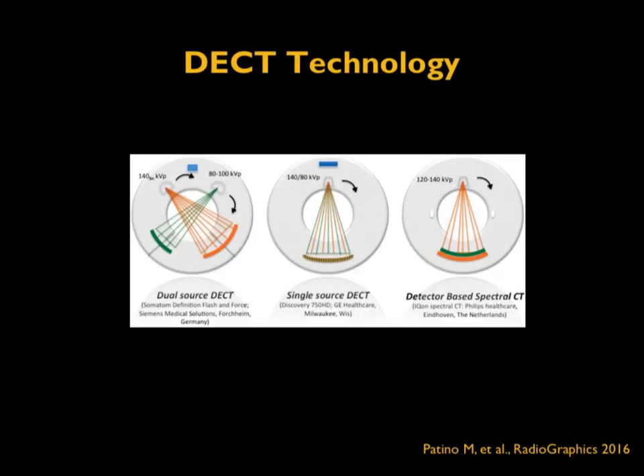In summary, dual-energy CT technology is achieved by four methods: first, two x-ray tubes such as in the dual-source system with two different detectors; second, a single x-ray tube with fast kV switching between 140 and 80 kV to obtain dual-energy spectrum; third, the same x-ray source with two different detector layers separating low and high energy; and fourth, the conventional method of scanning the same anatomical area twice at two different kV settings.